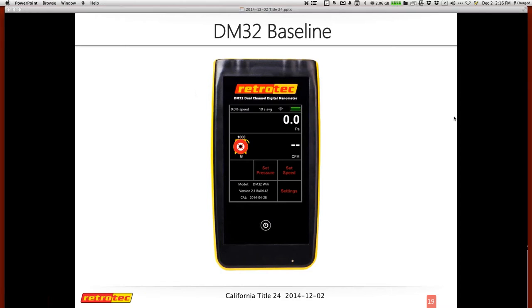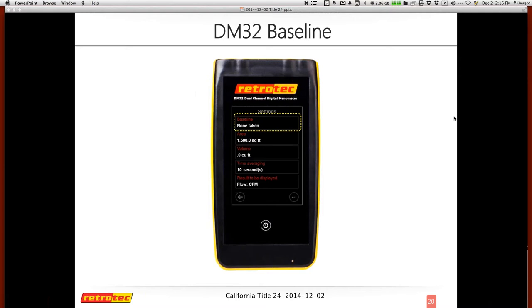On the DM32, to capture a baseline, hit Settings, go to the next page, and it tells you none have been taken. Press Capture Baseline, and a counter at the bottom shows how many seconds have elapsed. This is not a live gauge, just an illustration of how it's done on the DM32. You hit Capture and it captures the baseline. At this time the gauge does not keep track of all five baselines — that's a common request on the hit list for Retrotec in the future, along with upcoming software that will handle this automatically.